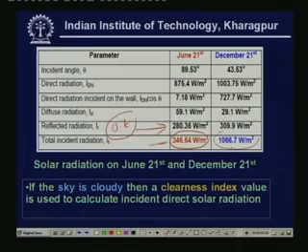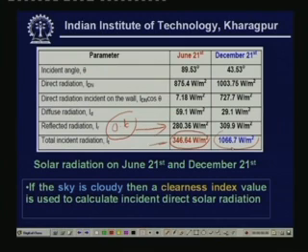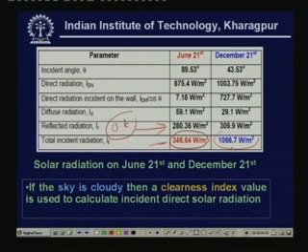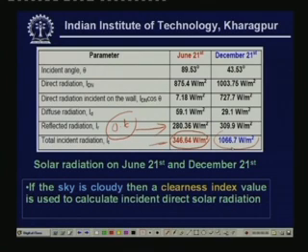Since we want to reduce heat load during summer and maximize heat transfer in winter, it is beneficial to keep windows and glass doors on the south side. This principle is used in passive cooling and heating techniques. These results hold for the northern hemisphere at 23° north latitude. If the sky is cloudy, a clearness index value (equal to 1 for clear sky, less than 1 for cloudy) is used to calculate incident direct solar radiation.